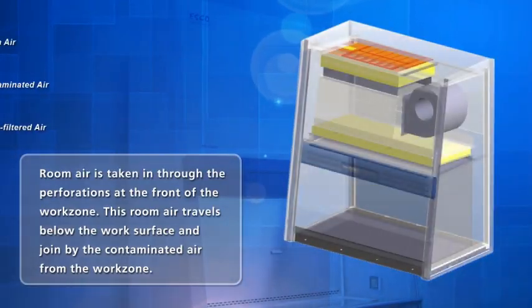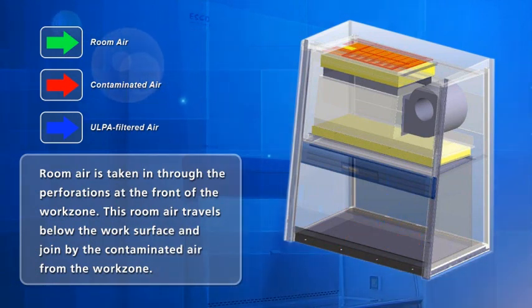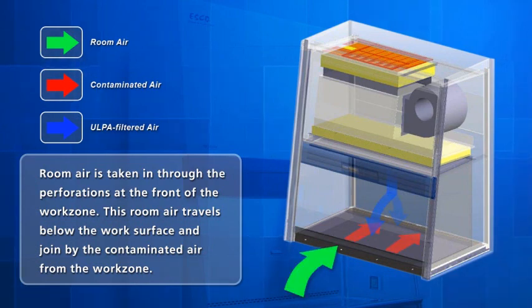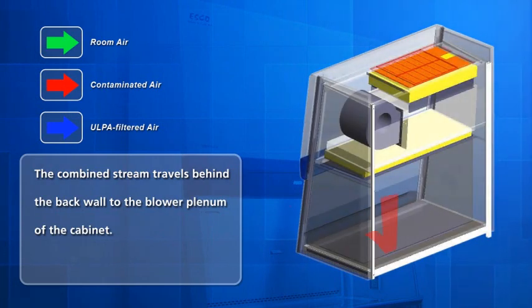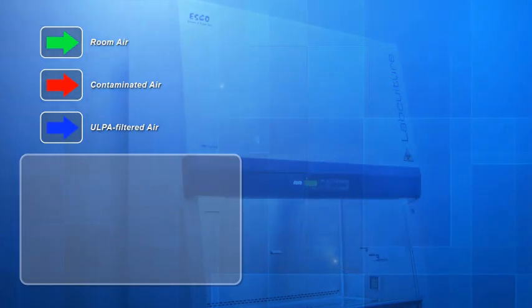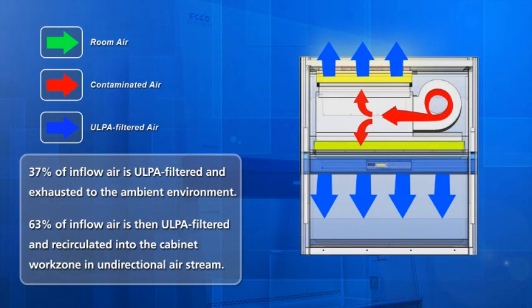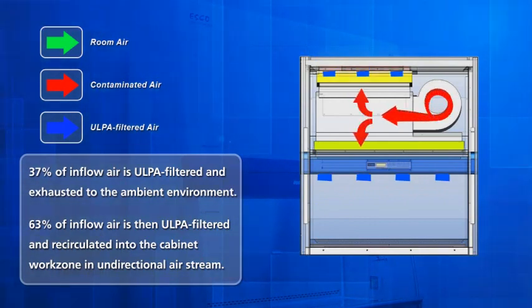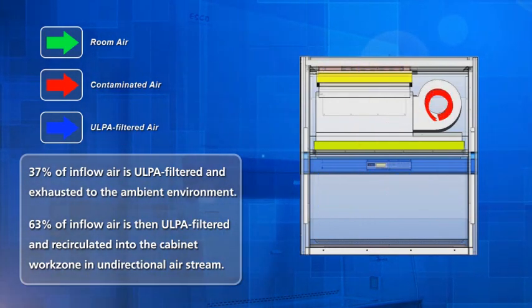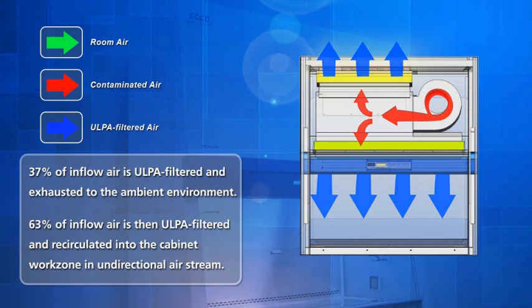A Class II Type A2 is a recirculating design biosafety cabinet. This means that room air is drawn into the cabinet through the front air grills, travels below the work surface through the back cabinet and into the blower plenum. From the blower, the air passes through the ULPA filters. Approximately 37% of the air is ULPA filtered and exhausted to the surrounding environment. The remaining 63% of the air is ULPA filtered and recirculated back into the cabinet work zone as unidirectional or laminar downflow air, providing a sterile and non-turbulent work zone environment.